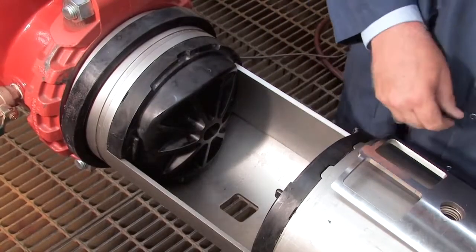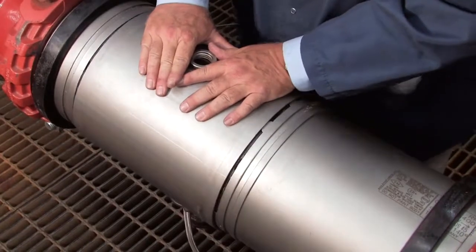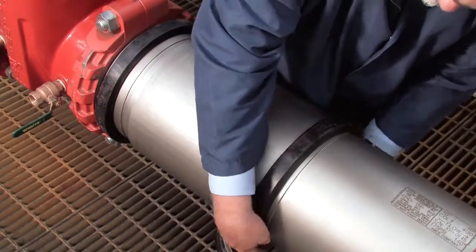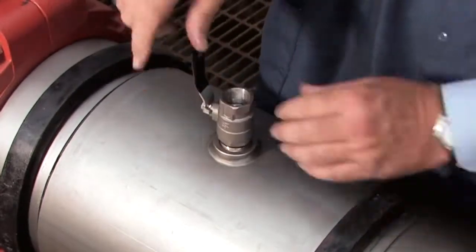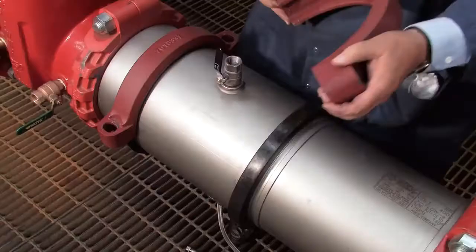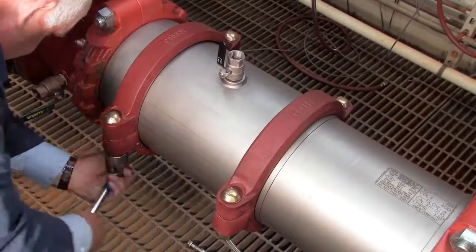With the checks replaced, reinstall the stainless steel retainer plates and close the cover sleeve. Replace the rubber gaskets around either edge of the sleeve and re-thread the number 3 test cock. Finish rebuilding the assembly by reinstalling the two couplings around the valve body and tighten the bolts evenly until they make pad-to-pad contact.